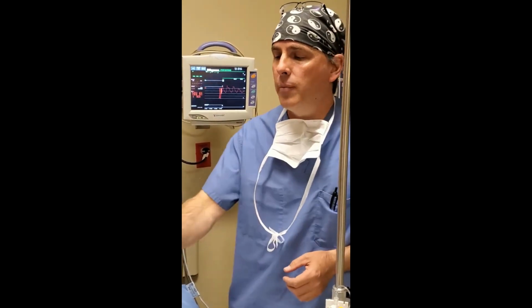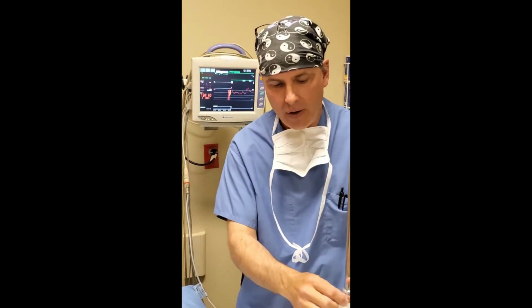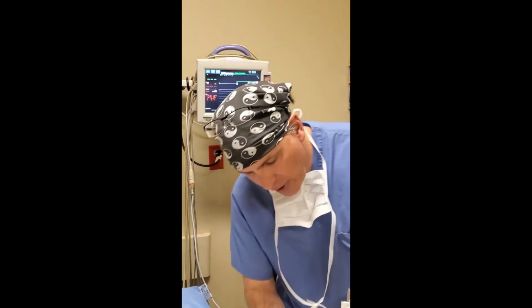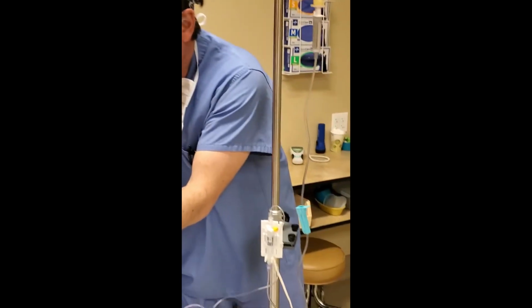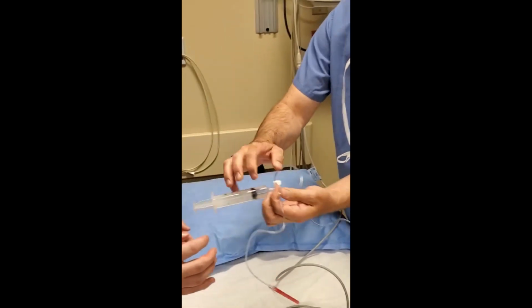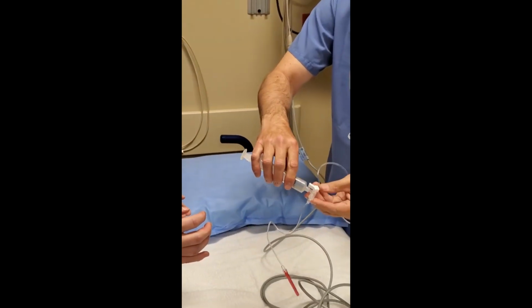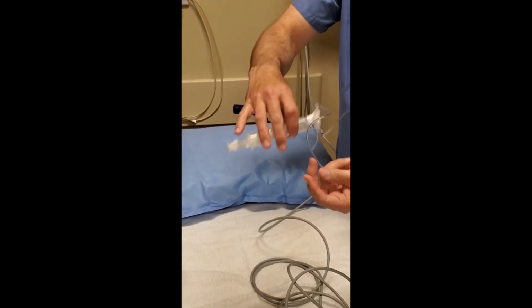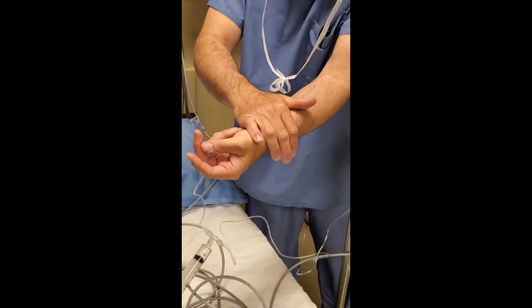So you always want to make sure your connections are nice and tight, that you always restore everything. When you walk away from this setup, check that the connections are tight, that the stopcocks are where they're supposed to be. There are several connections here you'll get to play with: this connection's tight, this connection's tight, that stopcock is open so it's connected to the artery, and that it's taped down well or sutured in well.